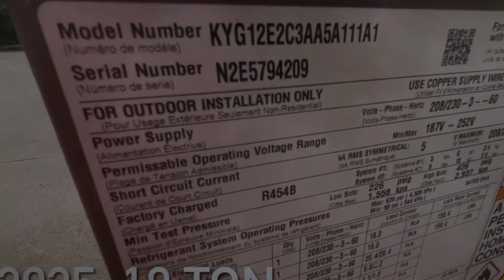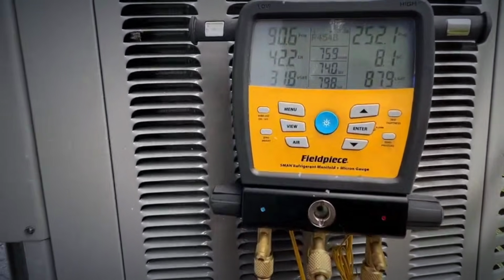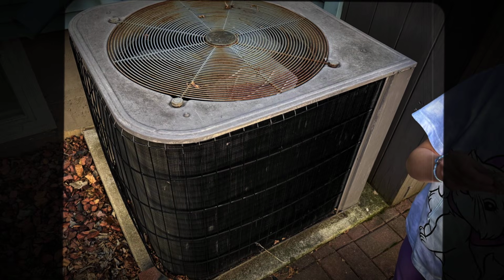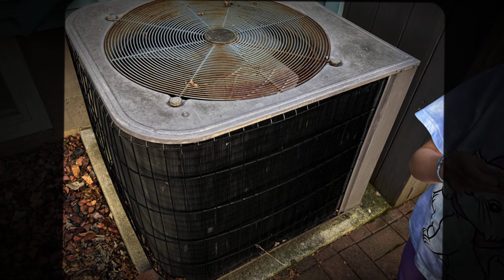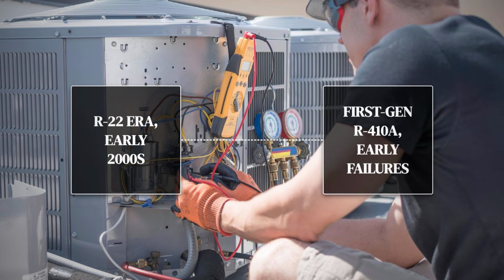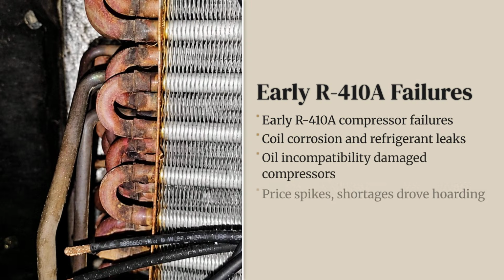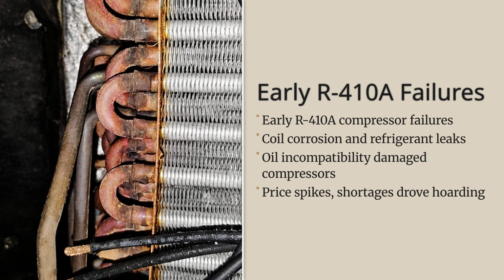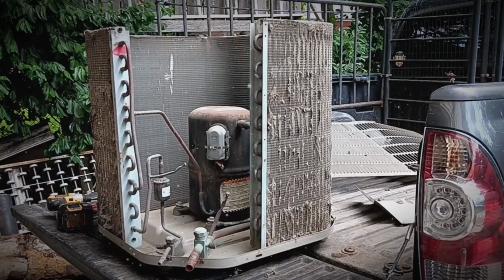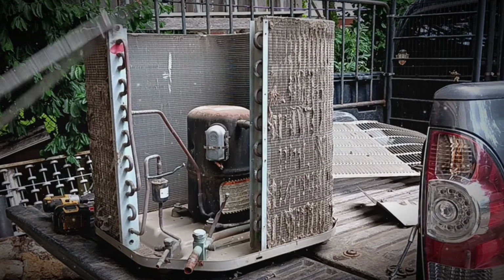That means every single R454B unit currently on the market is first-generation equipment. Every experienced HVAC technician alive remembers what happened the last time the industry forced a refrigerant transition. When R22 was replaced by R410A in the early 2000s, the first generation of R410A systems had widespread compressor failures, coil leaks, and oil compatibility issues that took manufacturers years to diagnose and engineer out of production.